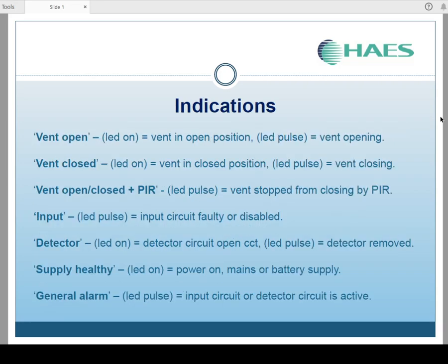You've got a vent open LED. When this is lit permanently, it means the vent is in the open position. When it pulses, it means the vent is opening or travelling. Same for the vent closed LED. When the LED is on, it means the vent is in the closed position. If it's pulsing, it means the vent is closing or travelling to that position. If you have vent open or closed plus the PIR LED pulsing, it indicates that the vent has been stopped by a PIR activating as a trap risk indicator. This can only be cleared by pushing reset on the panel.